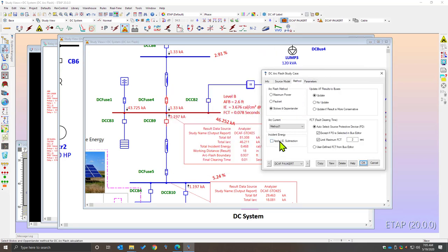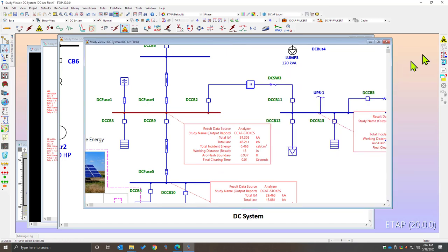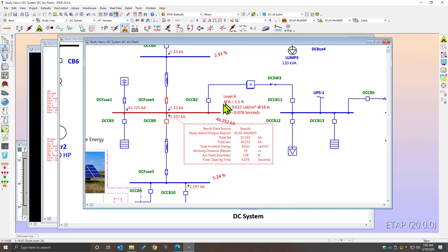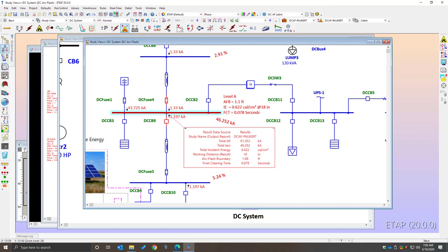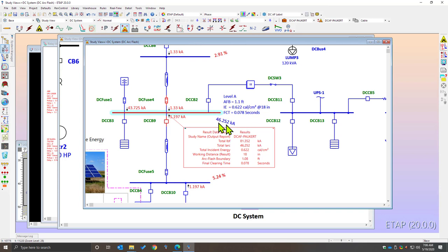Now let's apply our energy subtraction method to see if DC fuse one clears first followed by DC fuse four, or if results will be the same. Running our DC arc flash calculation again, the incident energy changes from 3.6 down to 0.622 calories per centimeter squared. With the subtraction method, DC fuse one clears first at a higher fault current allowing certain arcing energy to be let through, while DC fuse four — being slower to clear — has much smaller arcing energy because the fault current is lower.